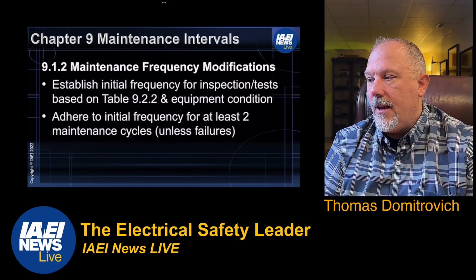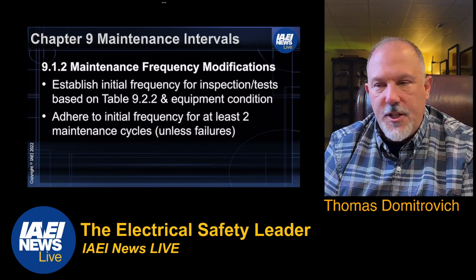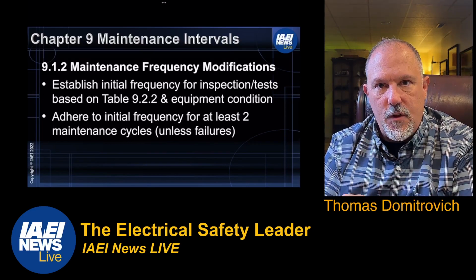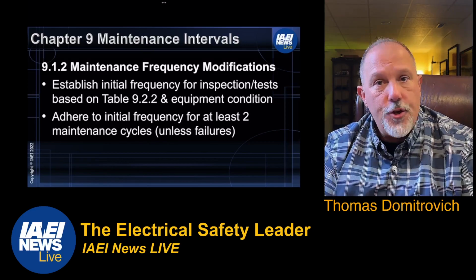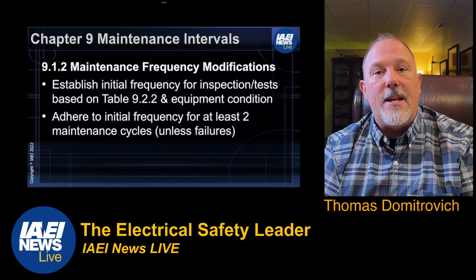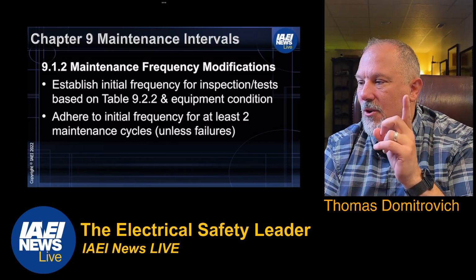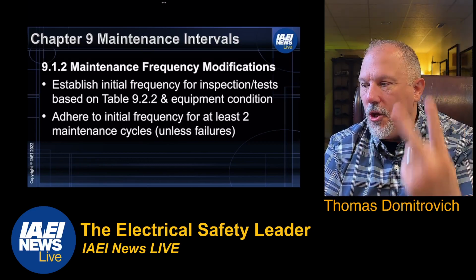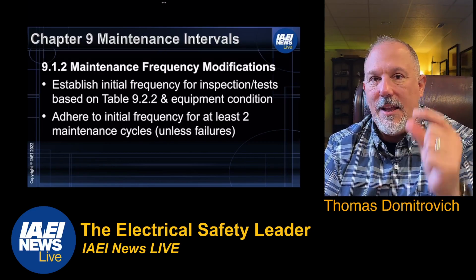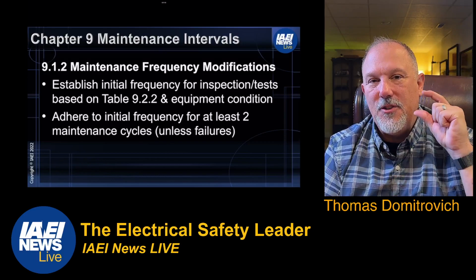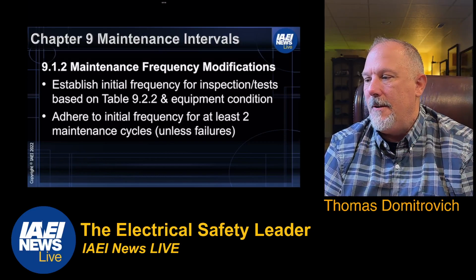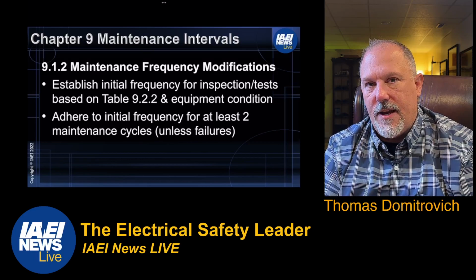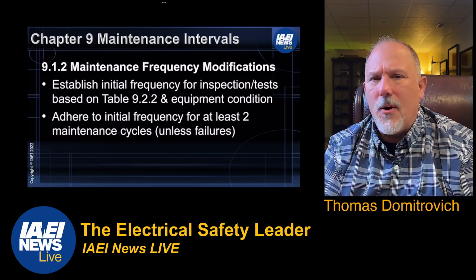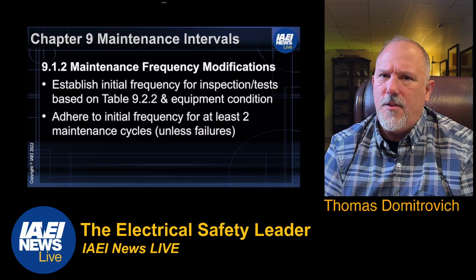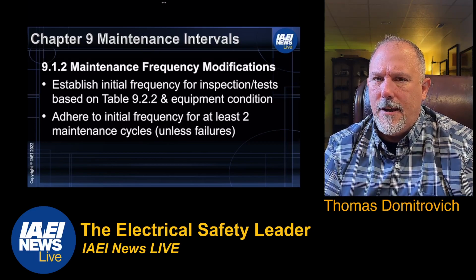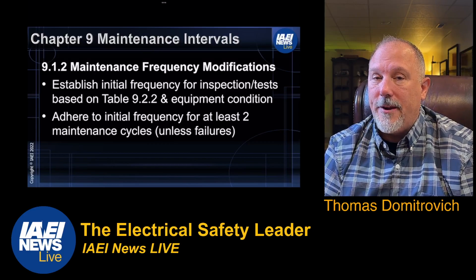9.1.2 tells us that you're going to establish the frequency for maintenance of your equipment—take a look at your grounding and bonding, and establish the frequency of maintenance for it in your power distribution system. Then you adhere to that initial frequency for at least 2 maintenance cycles, and I believe after that you can modify it. That's an interesting part of the puzzle. Go take a look at 9.1.2, read through that language, and let me know if you think it needs some clarity.